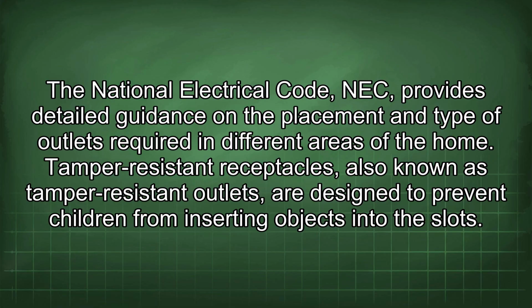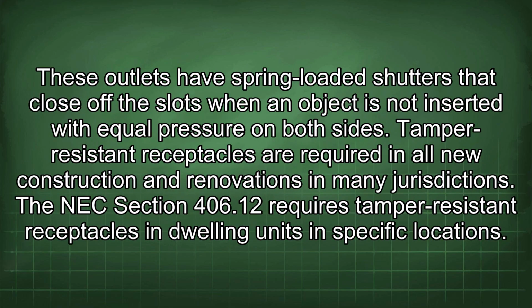the home. Tamper-resistant receptacles, also known as tamper-resistant outlets, are designed to prevent children from inserting objects into the slots. These outlets have spring-loaded shutters that close off the slots when an object is not inserted with equal pressure on both sides. Tamper-resistant receptacles are required in all new construction and renovations in many jurisdictions. The NEC Section 406.12 requires tamper-resistant receptacles in dwelling units in specific locations.